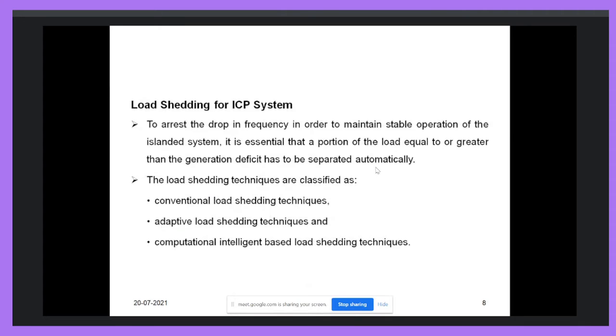Now, how can we design load shedding? The purpose of load shedding is to arrest the drop in frequency in order to maintain stable operation of the islanded system. It is essential that a portion of the load equal to or greater than the generation deficit is separated automatically. The purpose of the load shedding scheme is the automatic separation of the load which exceeds the amount of generation. The system must be automatic and disconnect the amount of load which is greater than the generation.